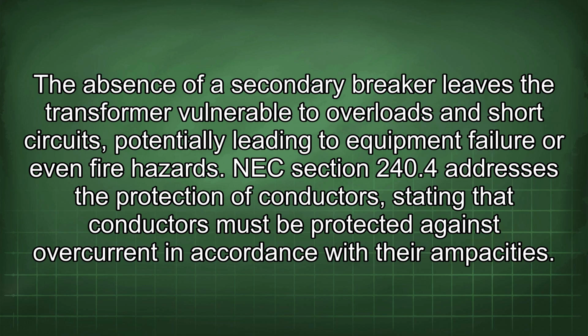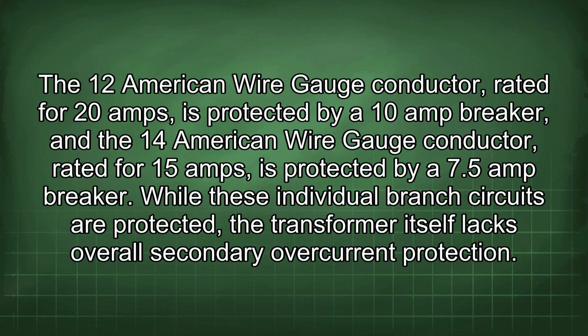NEC section 240.4 addresses the protection of conductors, stating that conductors must be protected against overcurrent in accordance with their ampacities. The 12 American wire gauge conductor, rated for 20 amps, is protected by a 10 amp breaker, and the 14 American wire gauge conductor, rated for 15 amps, is protected by a 7.5 amp breaker. While these individual branch circuits are protected, the transformer itself lacks overall secondary overcurrent protection.